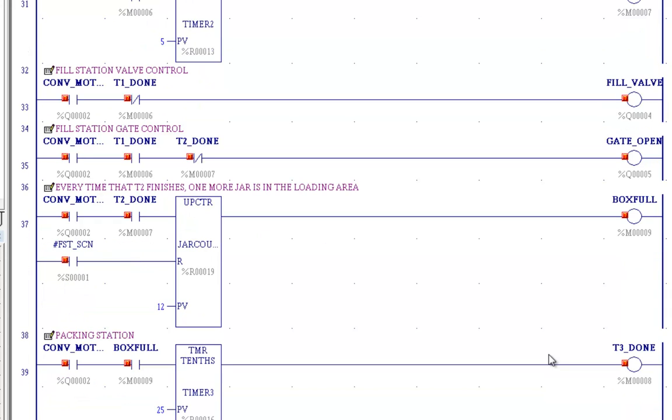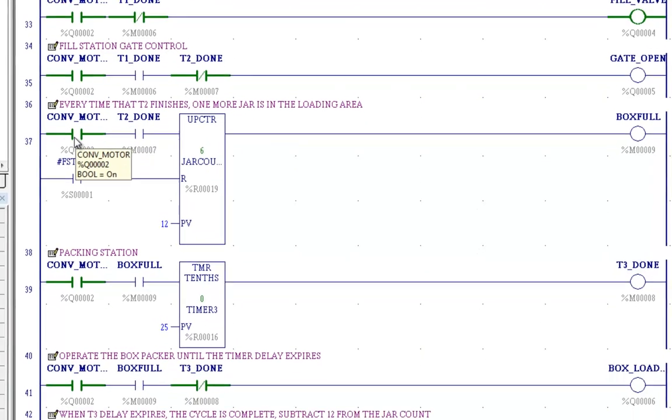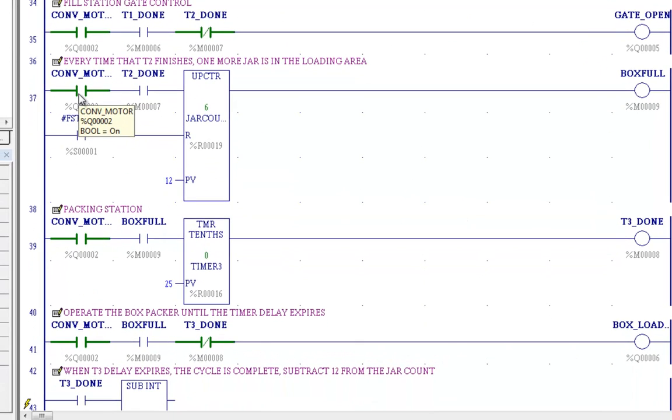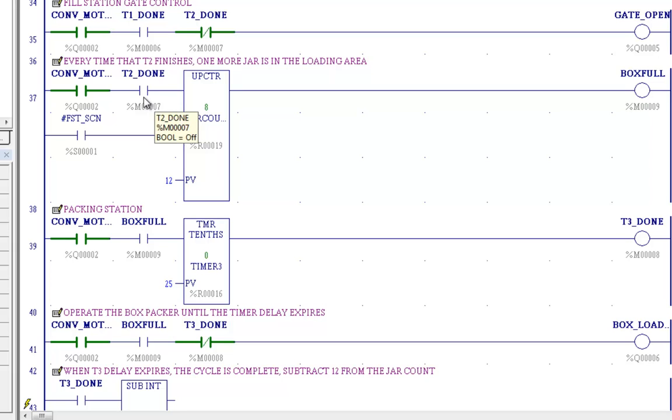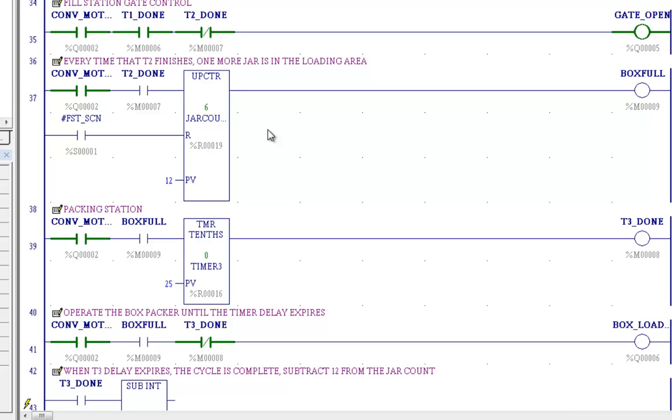Now we come over here. Conveyor motor running. And every time timer two is done, that means one jar is filled. And it's been moved through the gate valve and you can see our jar counter keeps incrementing. And if you watch there, you saw that for one slight moment that went to 13. It means we had 13 completed jars in the packing area. So this is important that we don't reset the counter. We're going to subtract from the counter. And you'll see that in a moment. There's 12 and that timer went back to one.